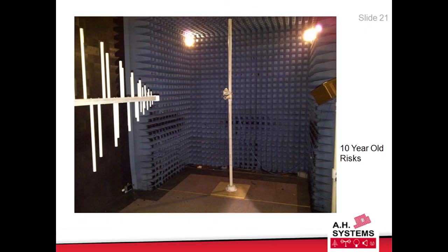Now let's look at this - we'll spend a short time on it. This is not atypical of what's out there, particularly for in-house tests. You can see it's set up as I recommend, with the boresight field probe in line. But looking at this, on the left-hand wall behind the antenna, it's all set up for up to 1 gigahertz testing - that's all ferrite tiles. This is what this chamber was initially, for up to 1 gigahertz testing. Then, of course, along came above-1-gigahertz testing, and you can see the guides themselves mounted with absorber.